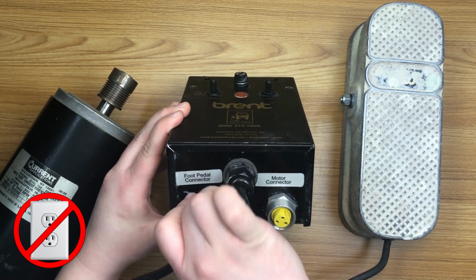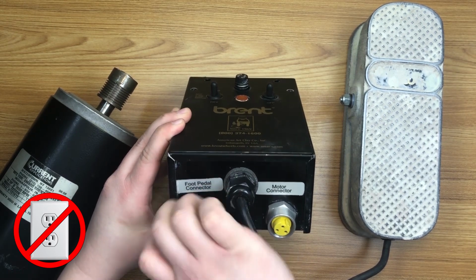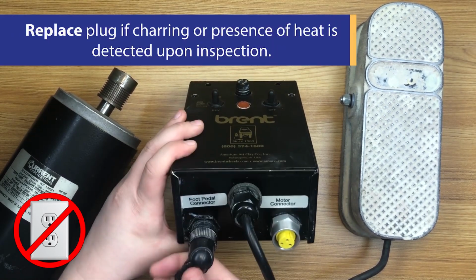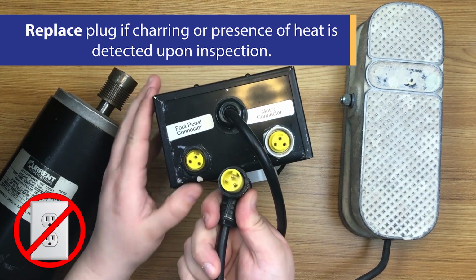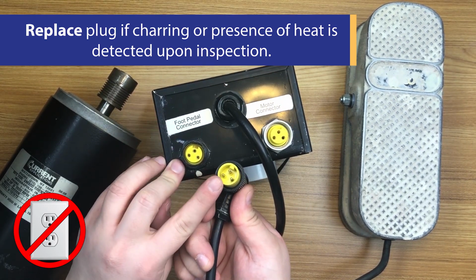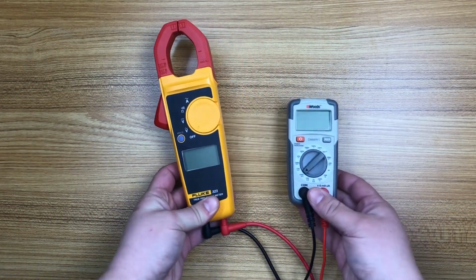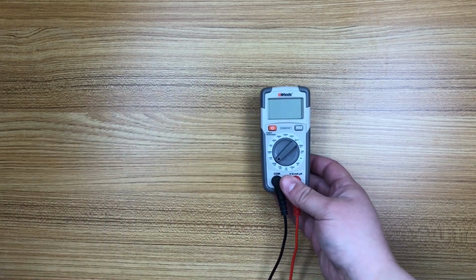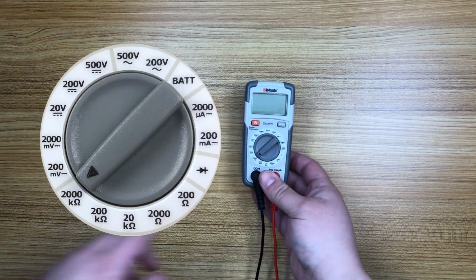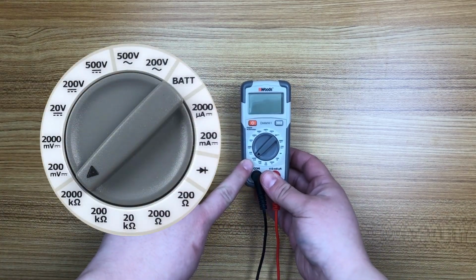Now, locate the foot pedal connection on the bottom side of the controller and rotate plug threading counterclockwise. Check both male and female sides closely for any signs of heat or discoloration. Some multimeters aren't able to measure the sensitive resistance circuit of the foot pedal. For this measurement, I'm going to use a multimeter that can measure ohms with a 200K setting.